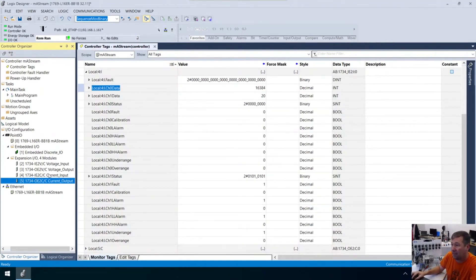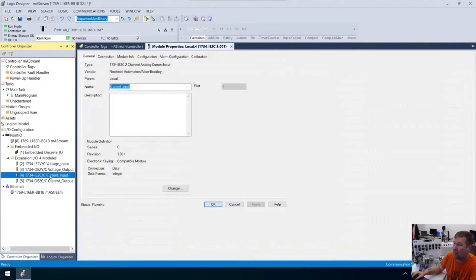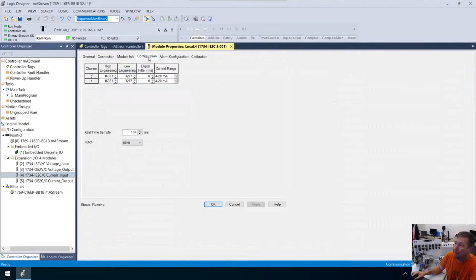If we double click on this module here, it's going to bring up the module properties. And then right here, we have the configuration tab. And if we look at it, our low engineering is 3277 and our high engineering is 16383.